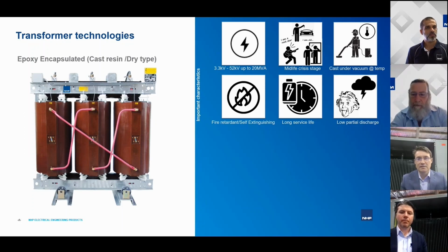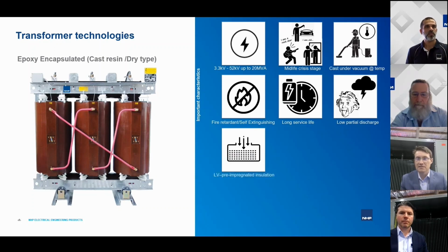The technologies, dry type versus oil, are so different. They're not comparable with regards to service life. And yeah, we can cover oil transformers' service life later, but it is generally considered as longer because you're able to monitor and replace the oil in the oil transformer. But when we're comparing cast resin to cast resin, this is where partial discharge becomes a very important factor. Mm-hmm. The other point to mention about cast resin transformers is the low voltage winding.